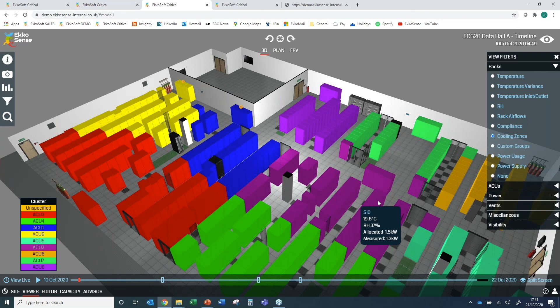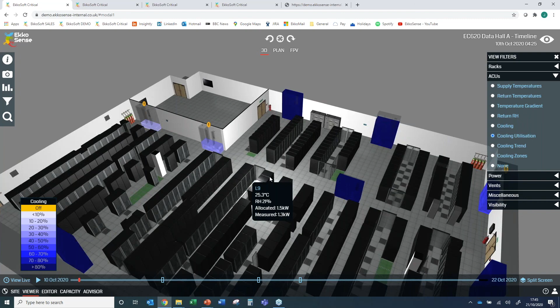What it's doing is linking the rack data and the cooling data, and it's learning which cooling units cool each rack and to what level. So it constantly learns the capacity within the rooms, not just as a total room, but within areas and pockets of the room: where are my actual capacity and availability. As I zoom out, you can see here, and the first thing that allows you to do is to understand the capacity of the cooling you have on the site, your true capacity, not assumed, but it also starts to bring in some other elements.